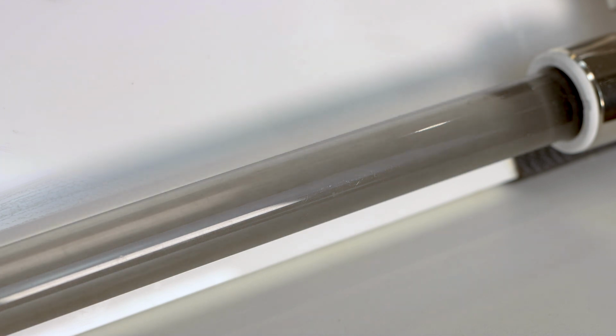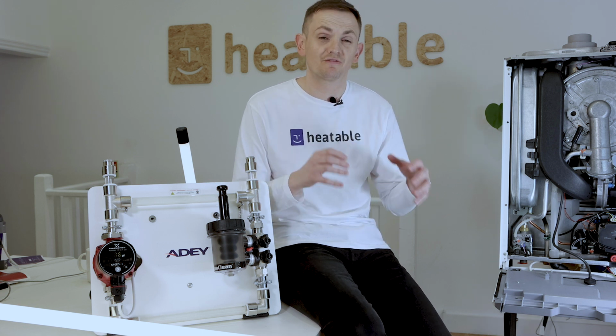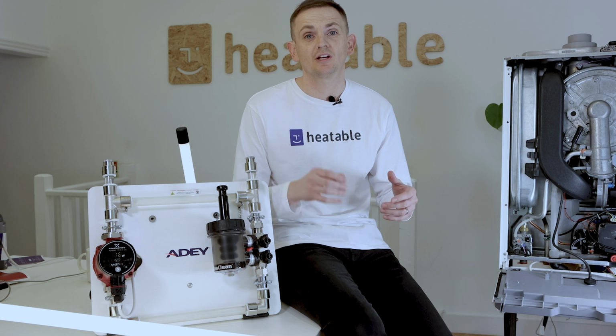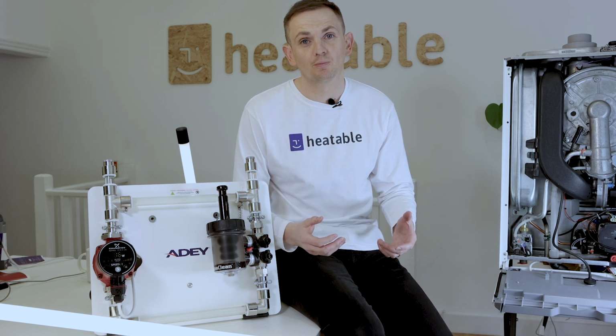If magnetite isn't captured, what happens is the metal particles enter the boiler, and new high-efficiency boilers use very, very narrow waterways. So these particulates clog the waterways, reduce the performance of the boiler, and ultimately break the boiler.